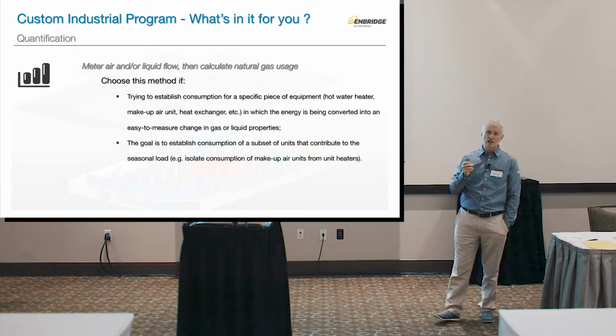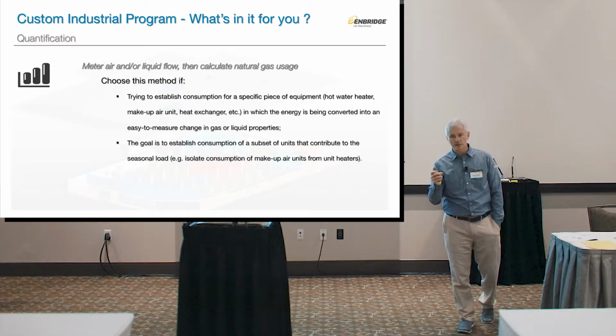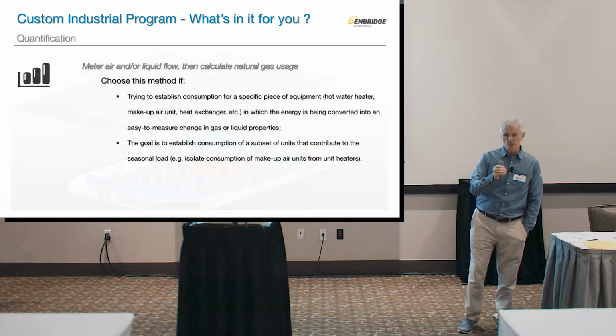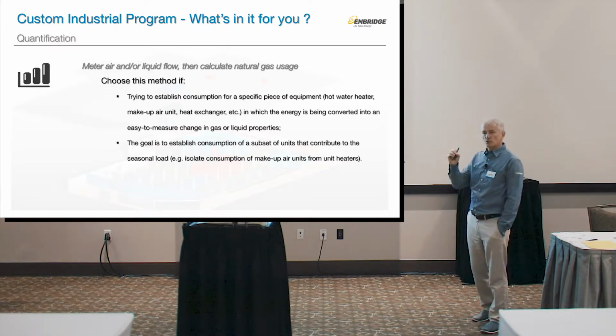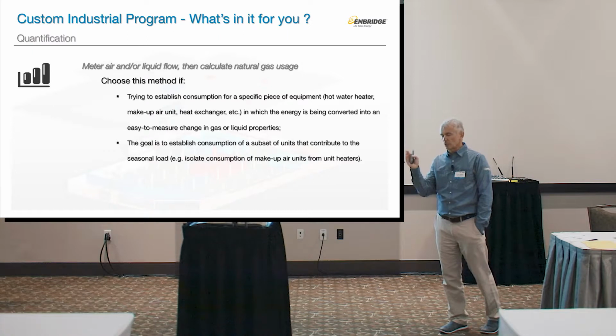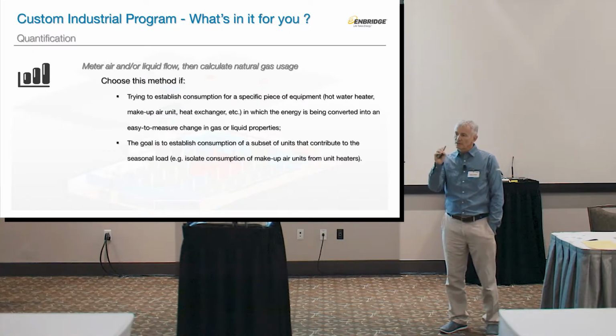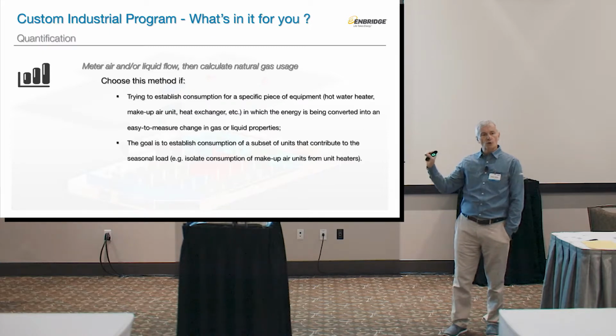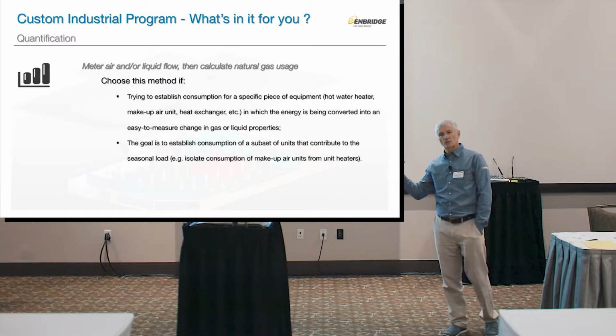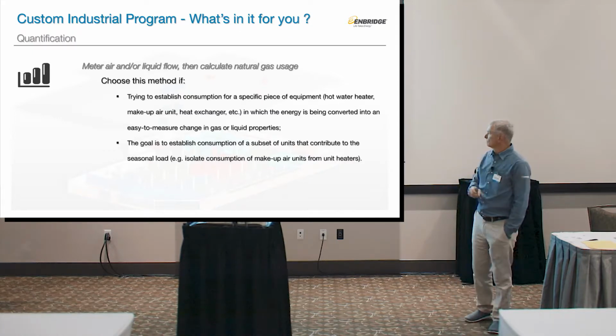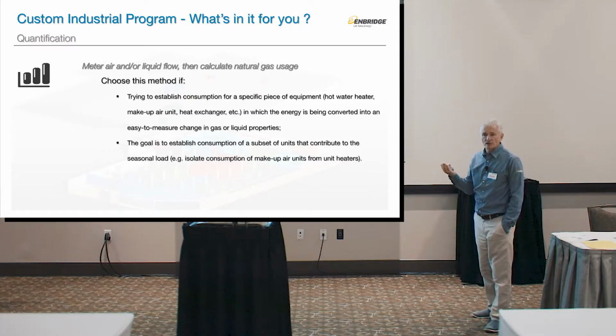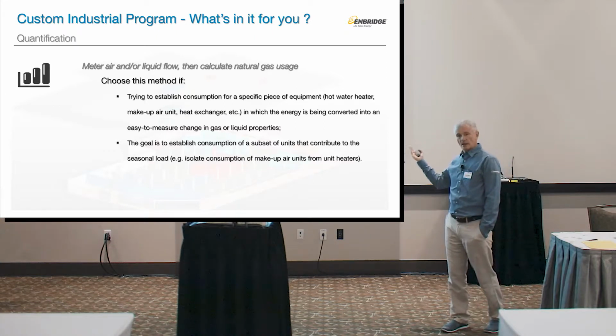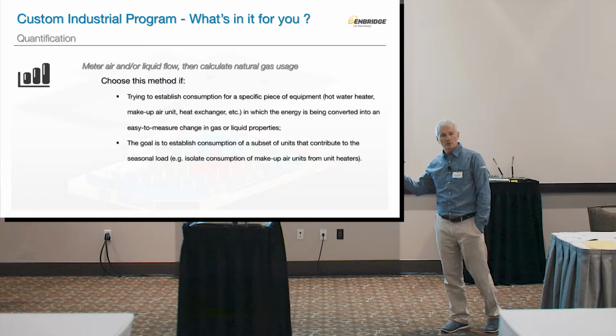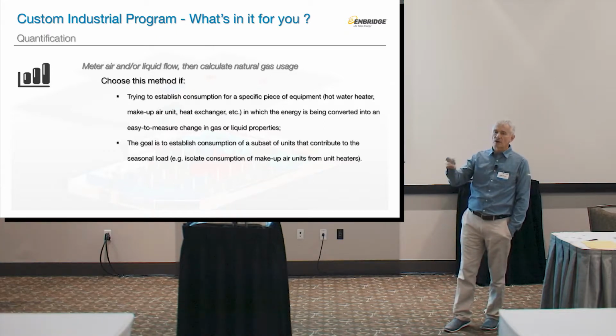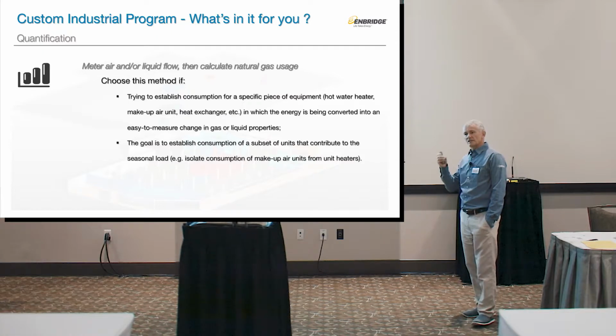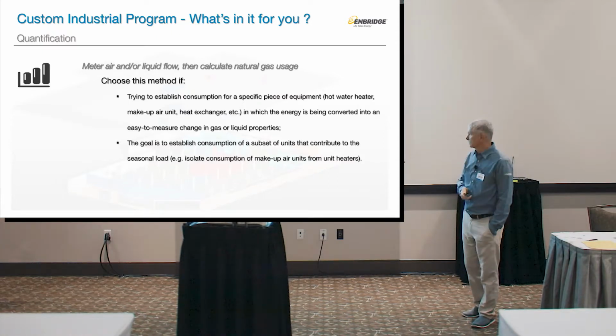It's an excellent method if you're trying to establish consumption of things like water heaters or makeup air units, not steam boilers. If you put a meter on air volume or on your water volume, you will get a very cost-effective way of measuring your natural gas. The goal is to establish the subset, for example, of units. You can do that on makeup air units in multiples, or you can do it on the water heater, one makeup air unit, however it suits you. And whatever it is, the savings will drive this.